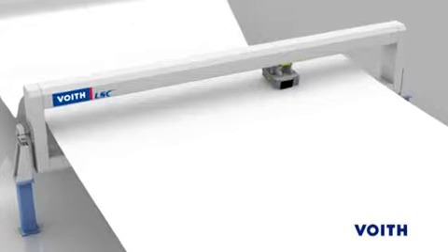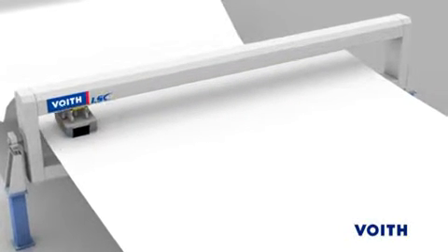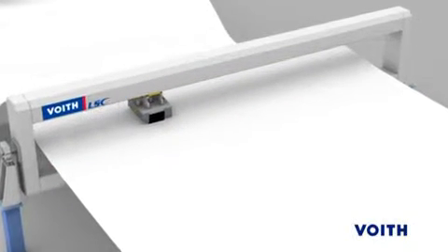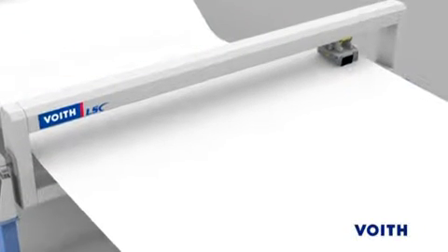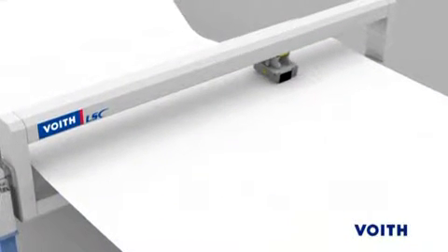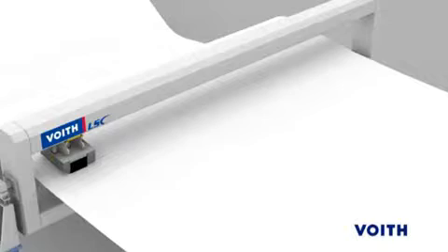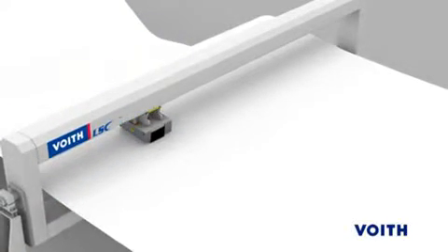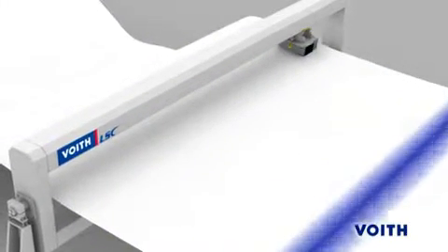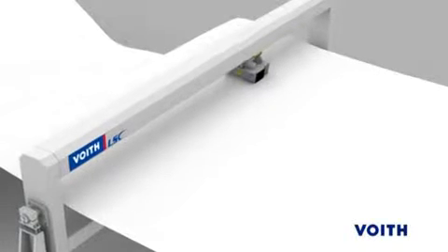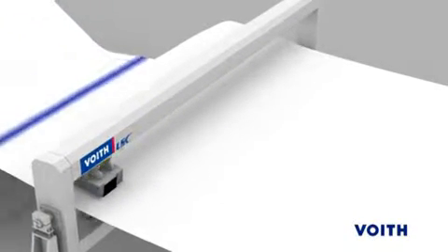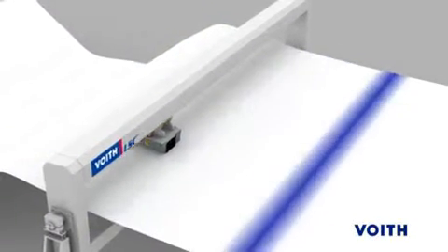Errors in the MD profile usually appear as periodic fluctuations. These cannot be corrected by CD profile control, but rather only by adjusting the MD actuators. Thus, although the scanner in front of the reel records the same effect as in CD profile deviations, another control behavior is required.